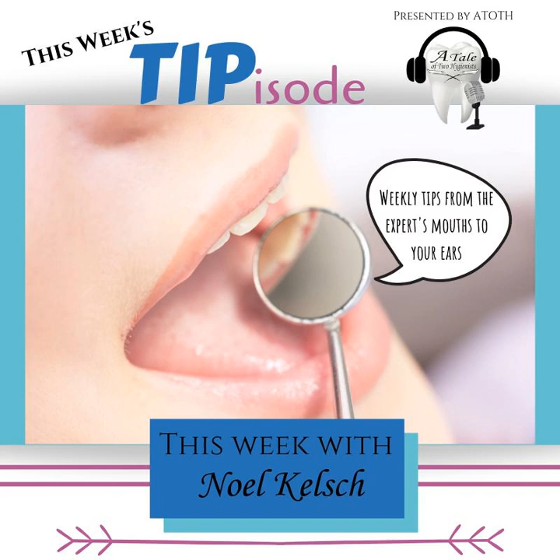Today we're going to talk a little bit about cold sterilization. Cold sterilization is a method of sterilization that requires the reusable semi-critical items to be immersed in an EPA-approved liquid chemical. These chemicals can include glutaraldehydes, hydrogen peroxide, and a variety of other materials. Single-use items can never be cold sterilized. They are not manufactured to be sterilized, and they may resist the process because of the materials which they are made from. So keep in mind that if it has the number 2 on the side and a slash through it, you can never cold sterilize.